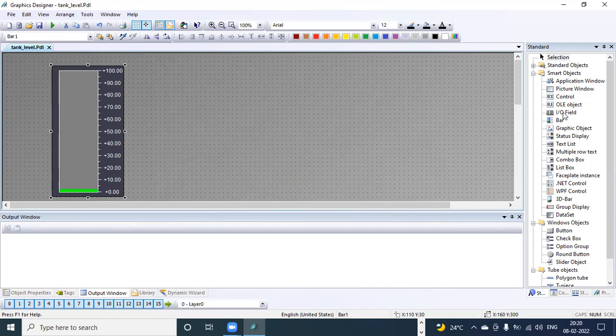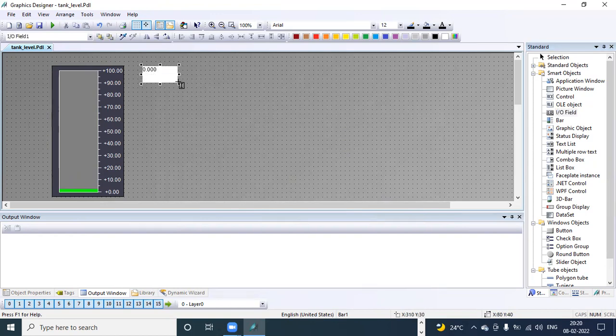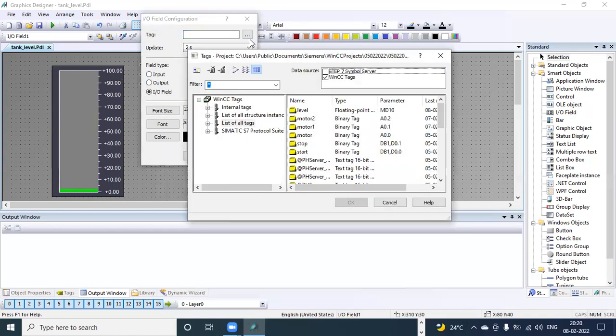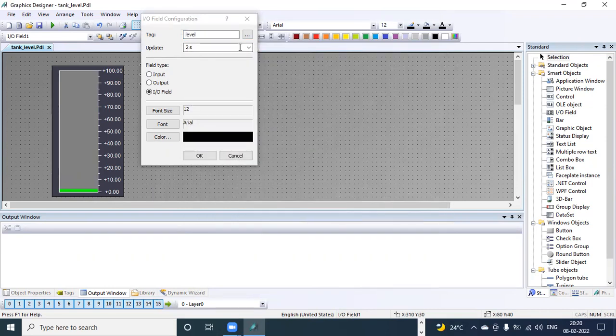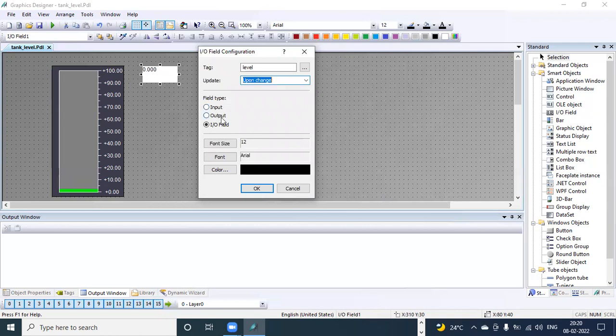Another option: from Smart Objects you can select IO Field. Drag it into the graphic window — it also asks for the tag name, so select tag "level". Update time: set to "upon change". Here you can see the field type — you can use it as input, output, or both. Both means you can enter a value like a set point and also see what is displayed as output. Select it as output.